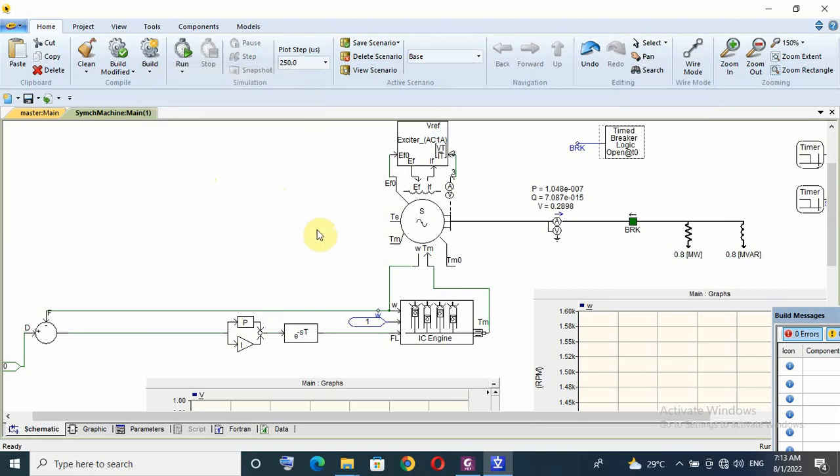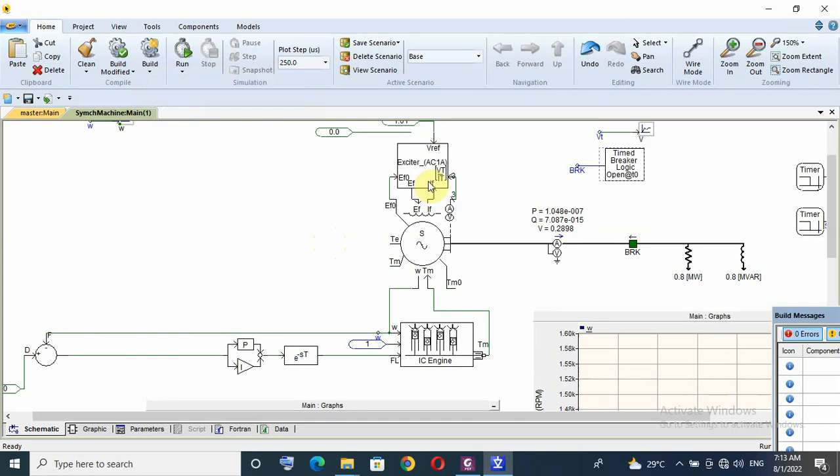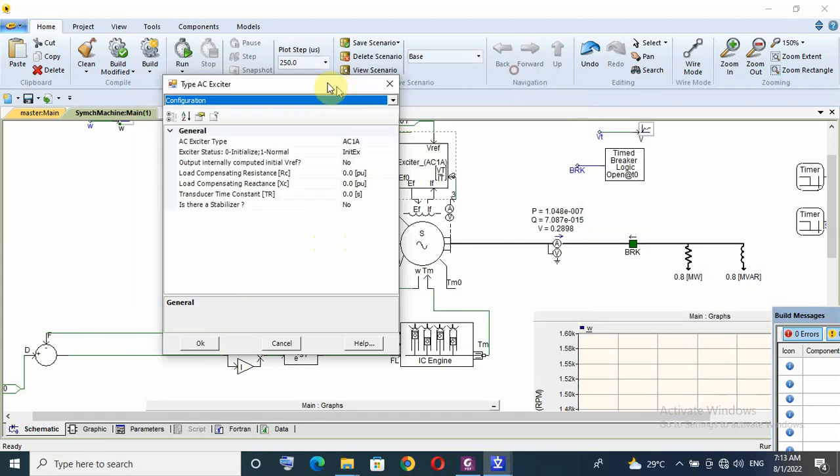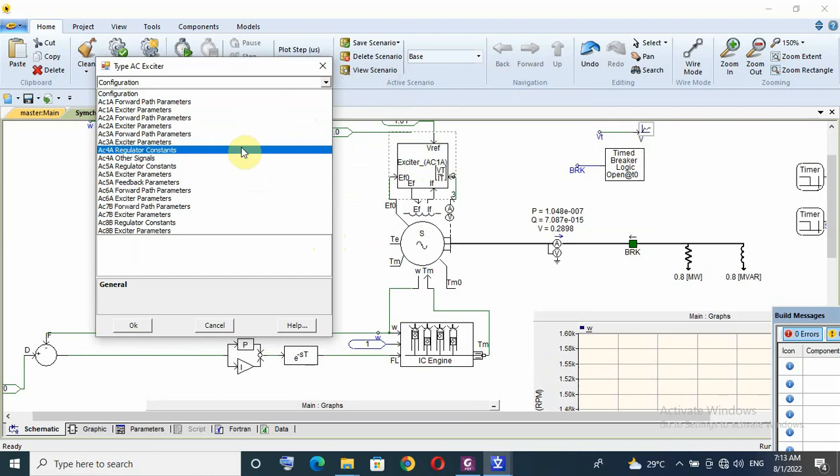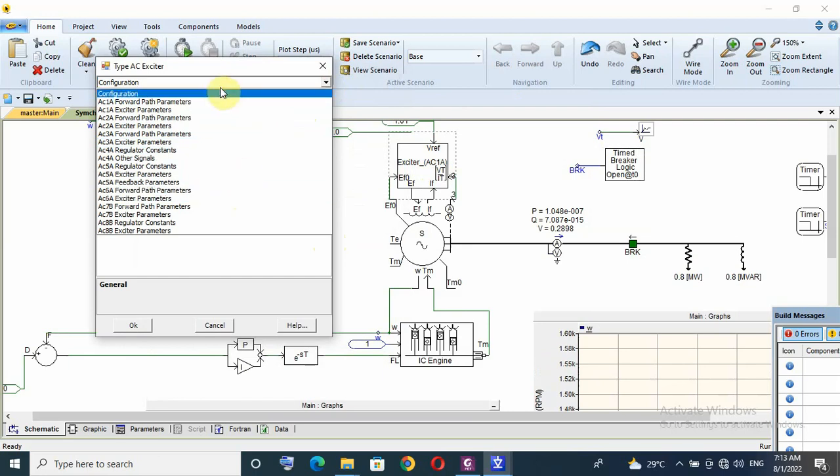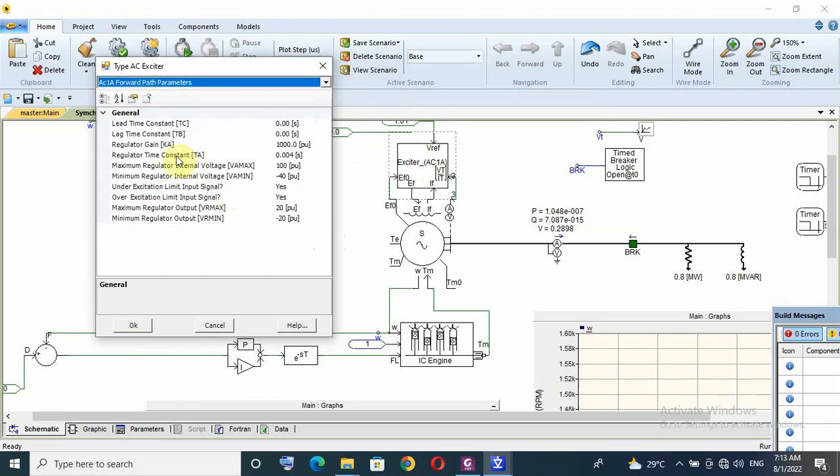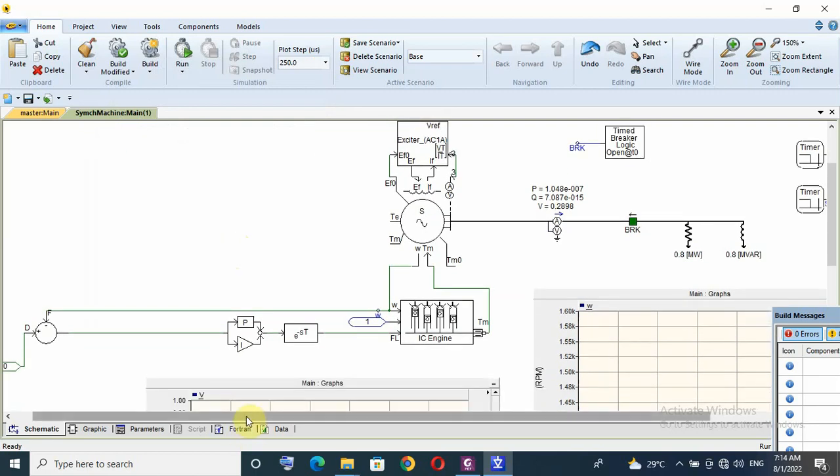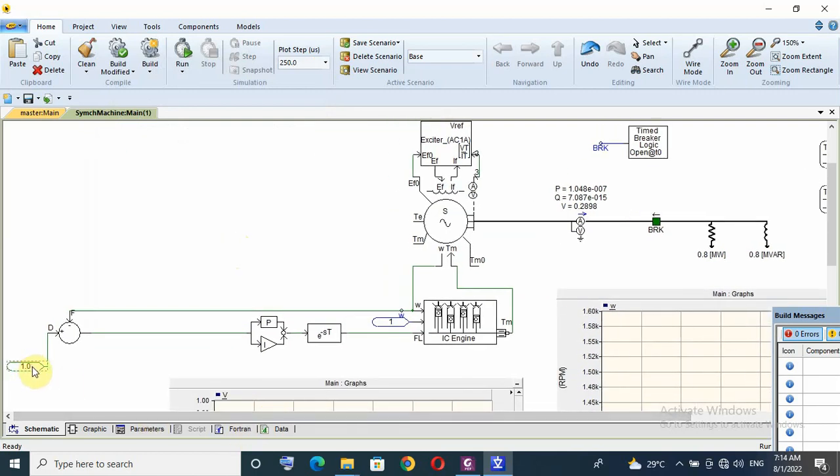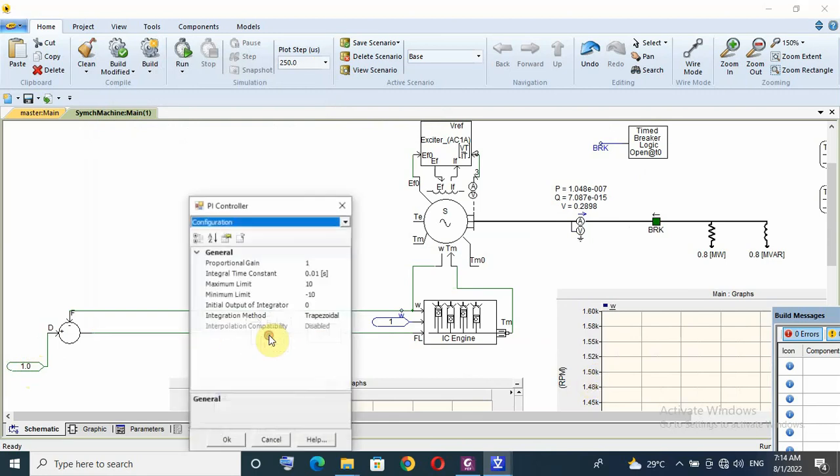I want to show the response of the governor or speed controller. For excitation system or AVR here I'm using IEEE model AC1A. Actually I have many models for IEEE exciters. I also have regulator gain proportional gain and regulator time constant or integral gain. My reference speed is 50 hertz or 1500 rpm.